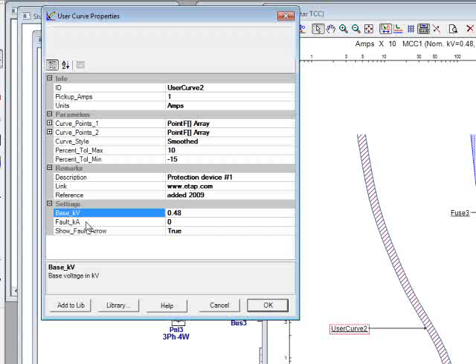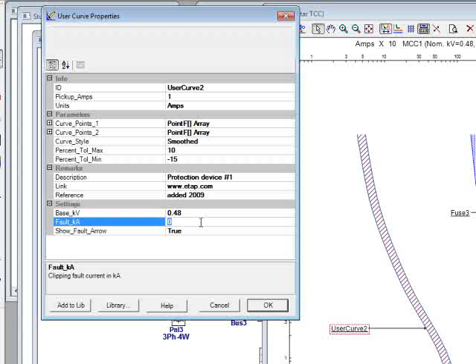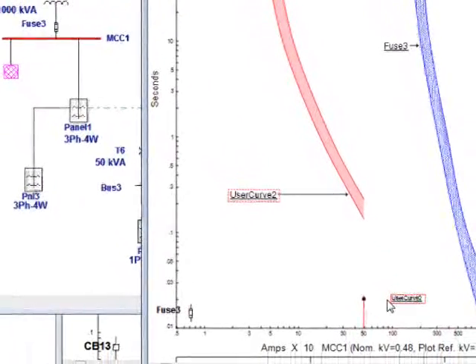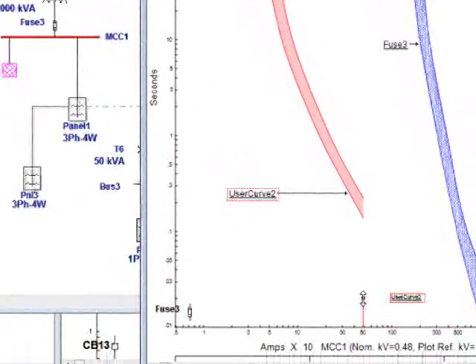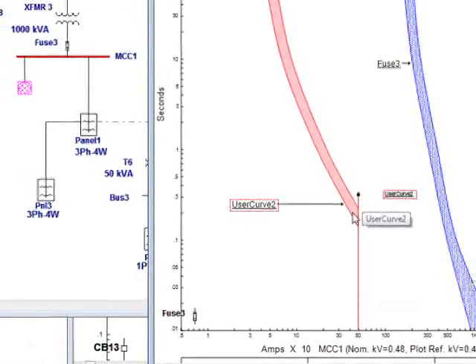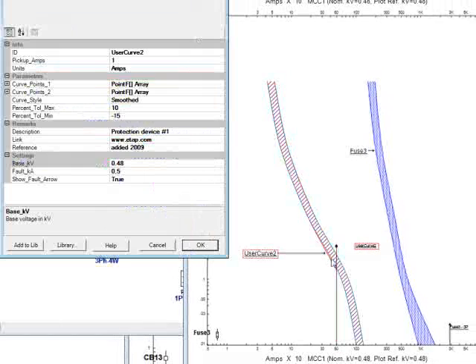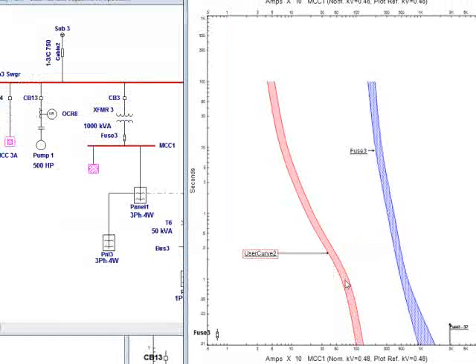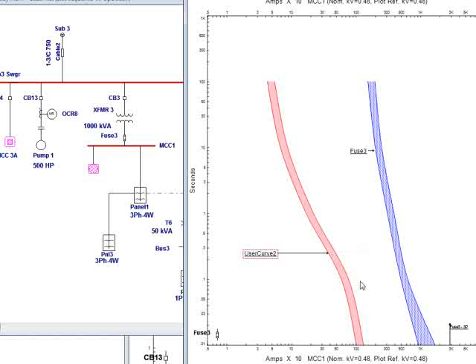Also, you can introduce the fault clipping current. Default value shows 0 if you introduce the fault KA current in the kiloamp. For example, if I introduce it as a 0.5 kA in this case, and if I click OK, now I'm going to have a user curve fault arrow, and I can show it. Or if I don't want to show the fault arrow, I simply can select this as false and click OK. So it doesn't show the fault arrow.